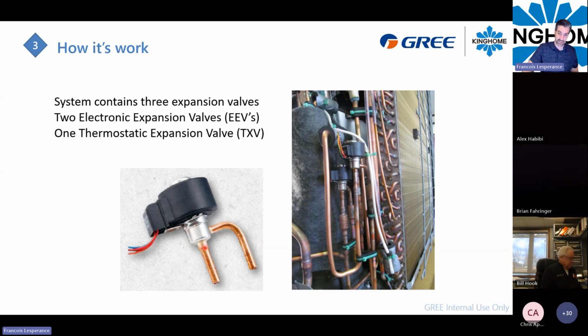So you have a small hole right here in the inlet of the valve, and then you can block that hole a little bit or open it a little more to have more refrigerant passing through that valve. So this kind of EEV has 500 steps. They call it steps. So it's the way you can open it. So at 0, it's fully closed, and if you have 500, well, it will be fully open.